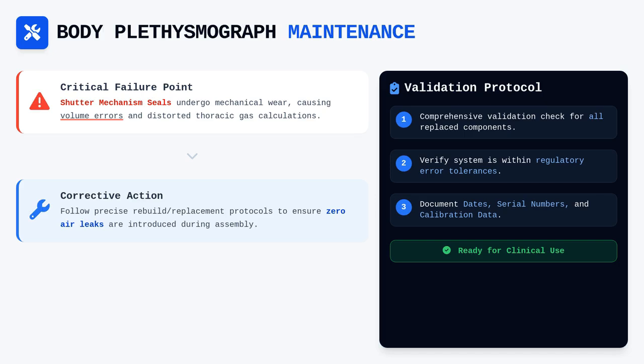An often overlooked, yet critical aspect of hardware maintenance is the structural integrity of the body plethysmograph, specifically regarding the shutter mechanism. The shutter seals are subject to constant mechanical wear during every panting maneuver, and small leaks here can introduce significant volume errors that distort the calculation of thoracic gas volume. When these seals begin to show signs of degradation, you must follow the precise instructions to rebuild or replace the assembly without introducing new air leaks.